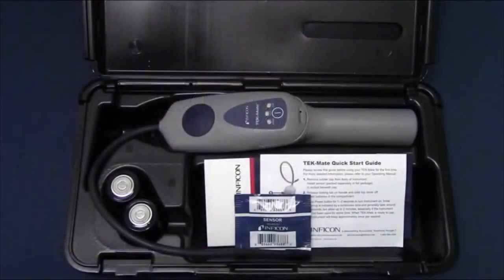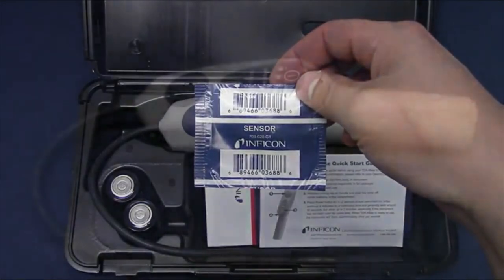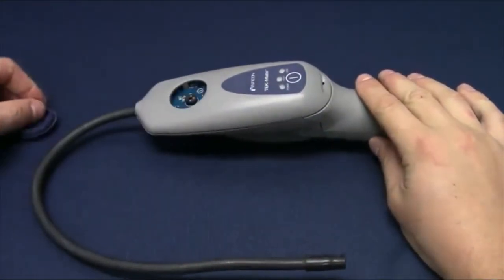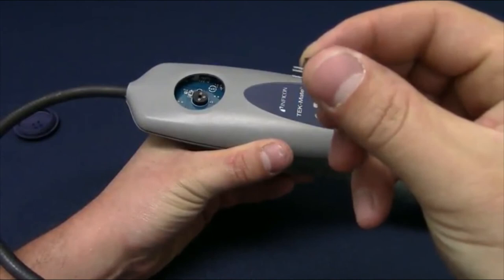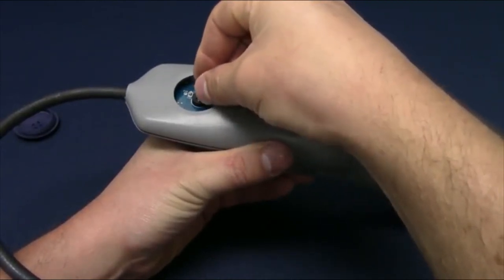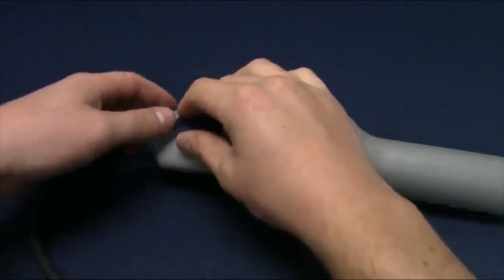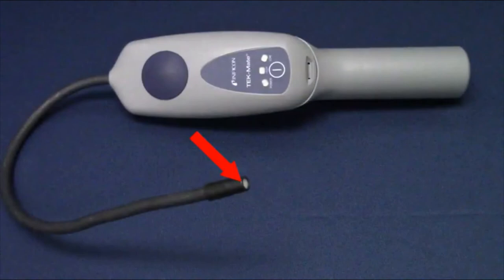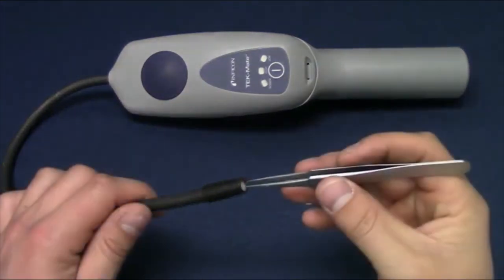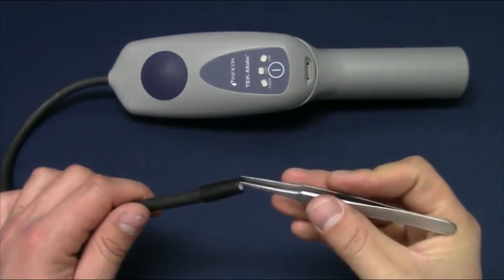All new TEK-Mates ship with a new sensor in a sealed package. A new sensor should last about 100 hours depending on application and refrigerant exposure. To install the sensor, remove the rubber sensor cover on the face of the TEK-Mate, cut open the sensor package, being careful not to bend the three small prongs, then install the sensor and reinstall the rubber cap. A filter is pre-installed in the probe tip; replace it with a replacement filter using a paper clip or small tweezers if it becomes dirty or clogged.